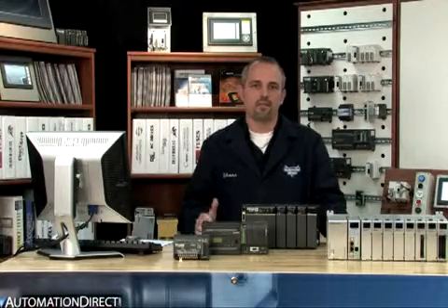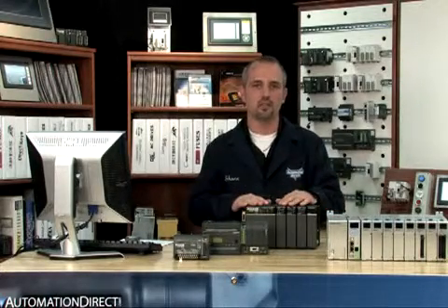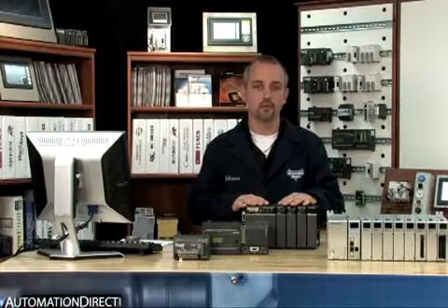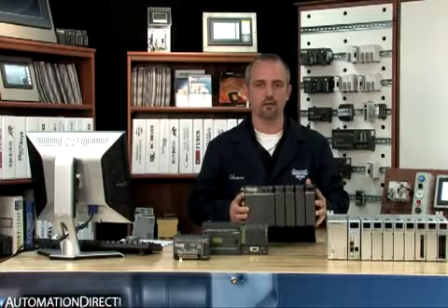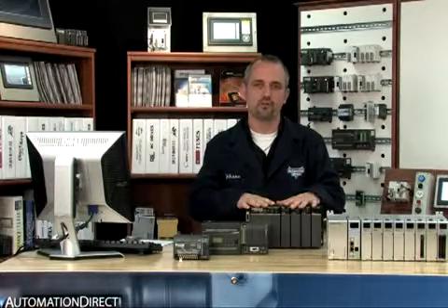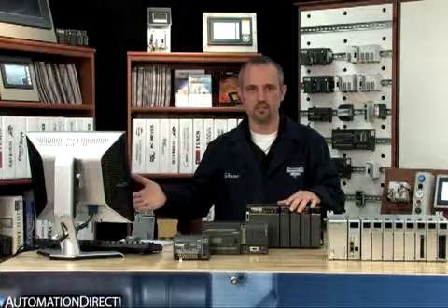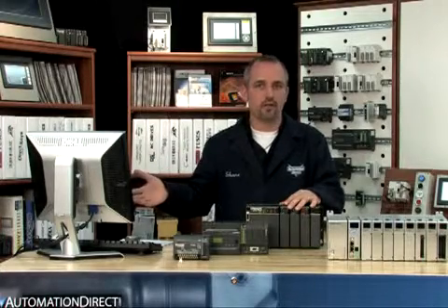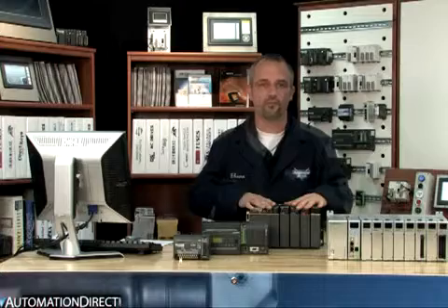Okay, that would work in most cases, but why hasn't PC-based control taken over in industrial automation? Well, the PLC has something the PC-based control system doesn't have. The PLC evolved into being industrialized and rugged with a modular footprint, a wide range of CPU capabilities, a wide variety of I/O types, and uses ladder logic programming software that is similar between manufacturers. In other words, PLCs in general do not have the computing power of a PC, and PCs typically don't have the versatility and ruggedness of a PLC.